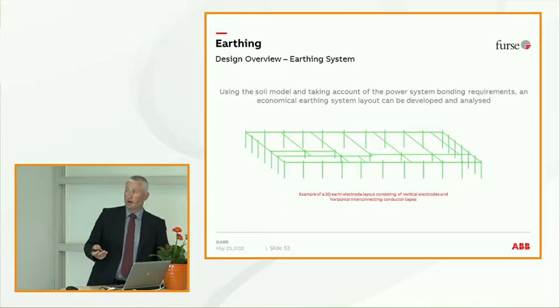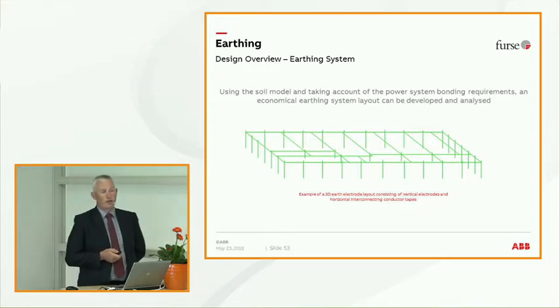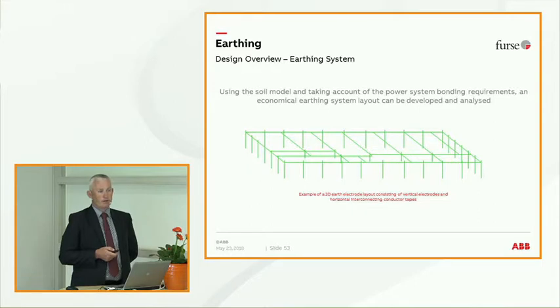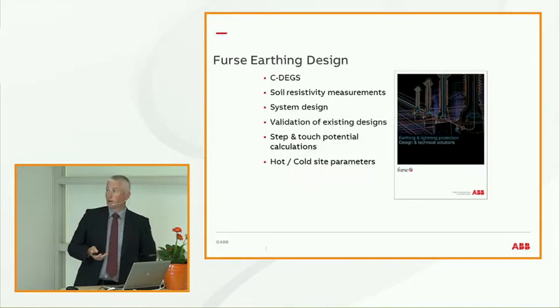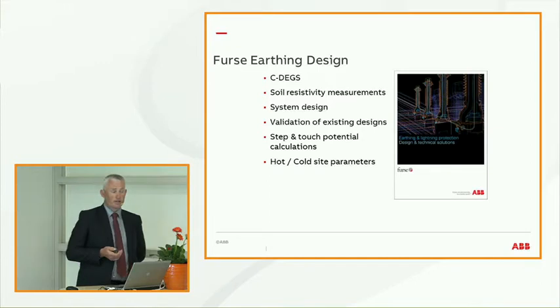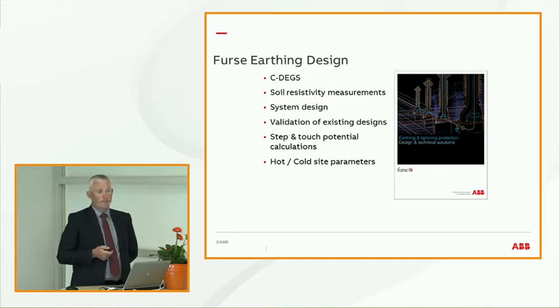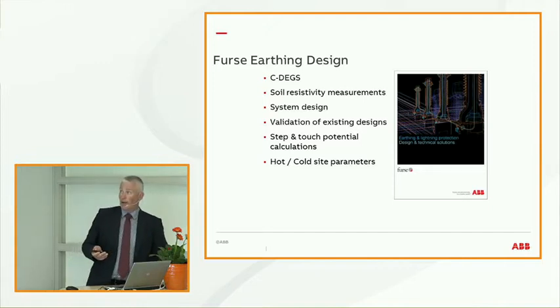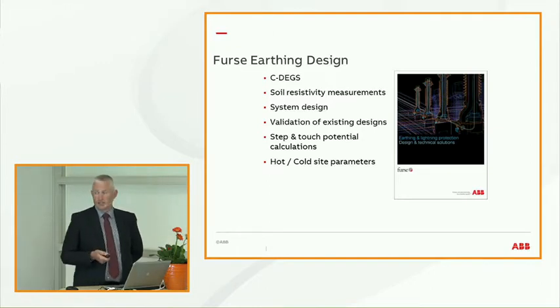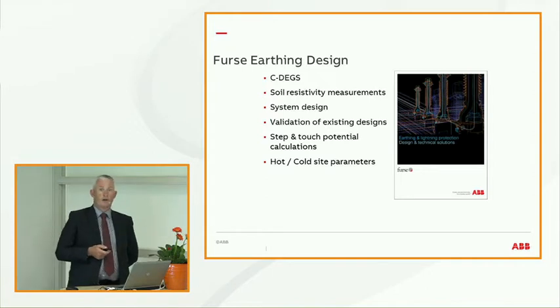A typical earthing design could be an array of conductor and earth rods. That's been determined by the soil resistivity, the fault currents, and other factors taken into consideration. Like I say, CDEGS, that's a worldwide application that's recognised for earthing design, and we get involved with validation of existing designs and step and potential calculations. I notice my time is about running out, so I'll cut it there.